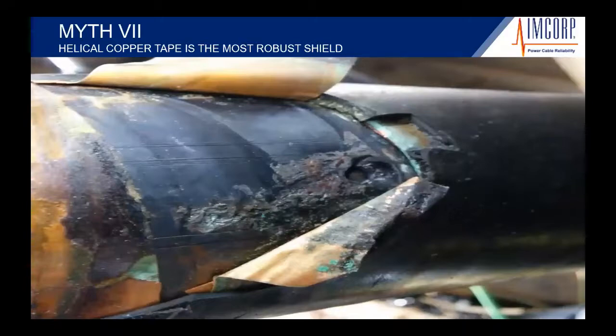Now, when we see issues at terminations, it's an opportunity because today we know that we can mitigate or repair the end of the termination. Here you have a cable that this particular one was 1500 MCM. We worked with the cable accessory manufacturer as well as the cable manufacturer to develop a solution for this. We removed each one of these components, took off the jacket, took off the metallic shield and the semicon, and we were left with some insulation that had been pretty damaged. We were able to buff that out, sand that out nice and smooth, and with the manufacturer's components, had them rebuilt that. We tested this cable at 2 times operating voltage with our testing system, and it held voltage and it met factory standards.